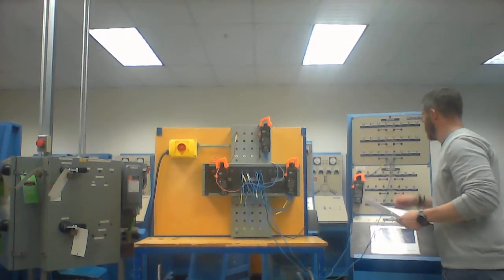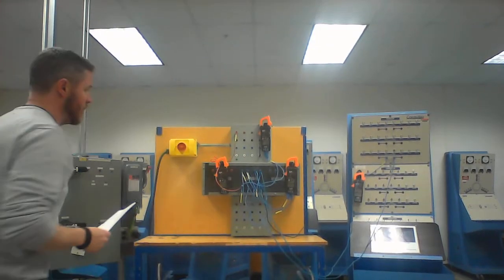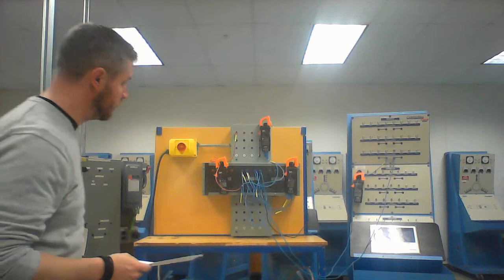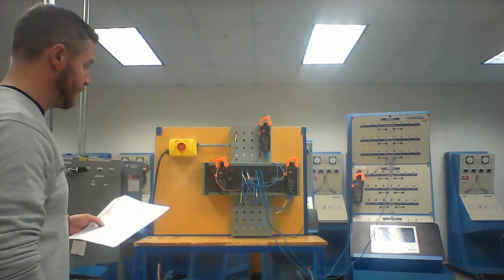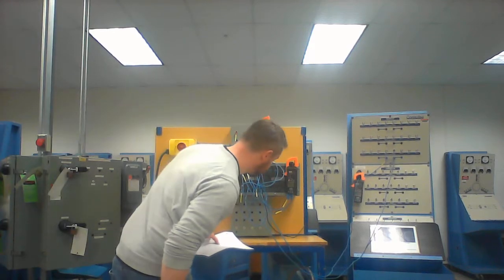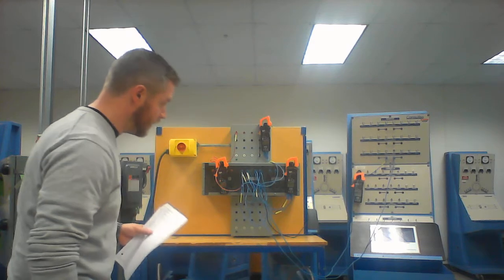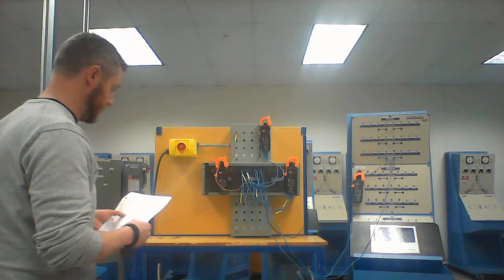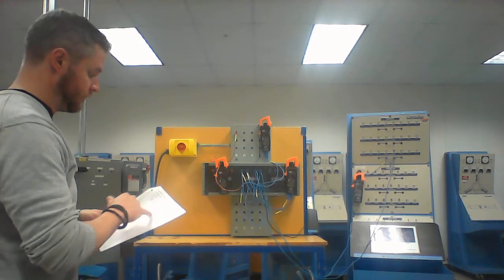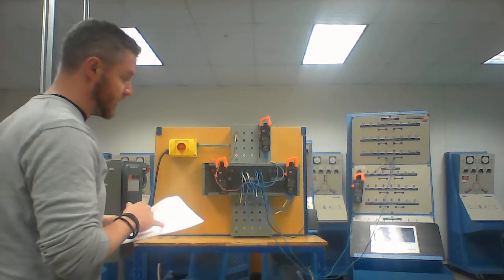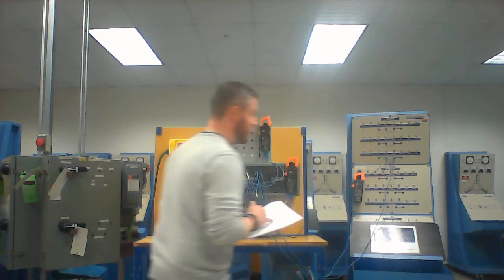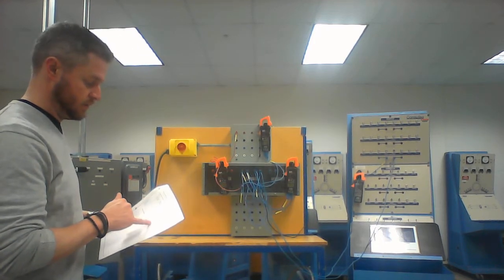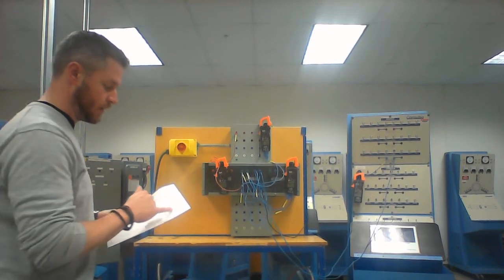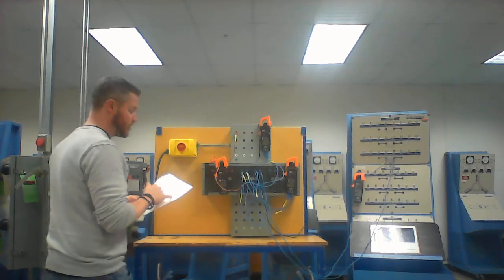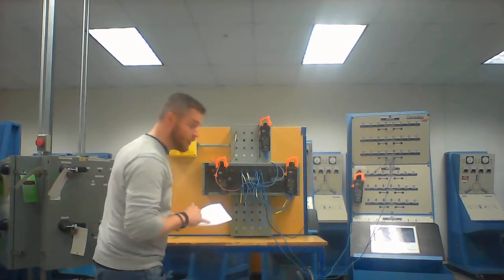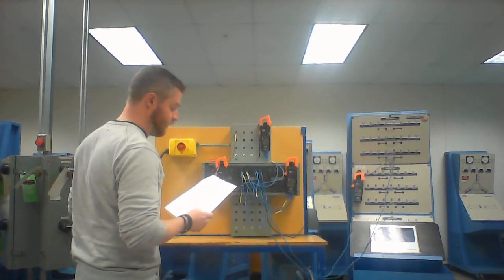Now we'll do the same thing with a 220 ohm resistor. Okay. Primary voltage, 115.9. We're getting a little lower here. Secondary voltage, 181.6. Calculated voltage ratio, we'll do that later. Excitation current is going to be the same the whole way through. Measured secondary current, 0.78 amps. Calculated primary current, we'll do that for you in a second. And measured primary current, 1.4 amps.